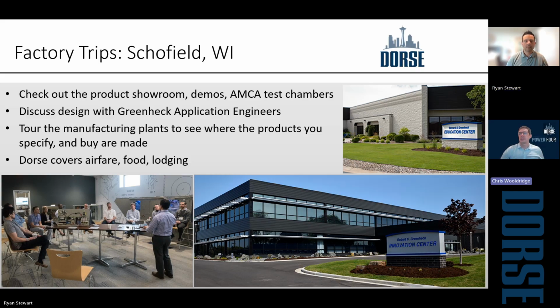Yeah, and that's something that's wonderful with the Greenheck system, where we can provide all of the components and ensure that it's all going to communicate properly. I've worked on numerous projects where the hood manufacturer was someone else, and then the engineer would spec and the contractor would purchase the Greenheck equipment for fan and makeup air. And there was always a disconnect of what the expected output signals were for maybe the hood controller to our equipment. So it can be done. It's just one extra step of communication from who's providing the hood controls or at the hood and the fan. So that's what we like to say, we're a single point source. We can do it all and ensure it's all going to work.